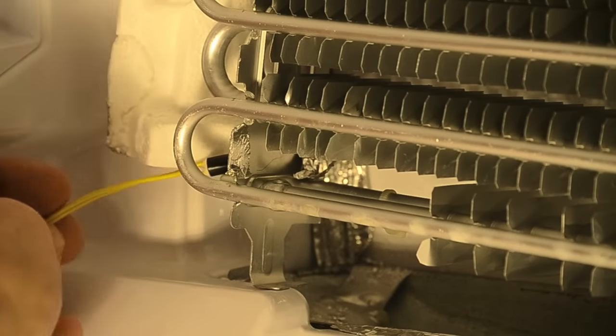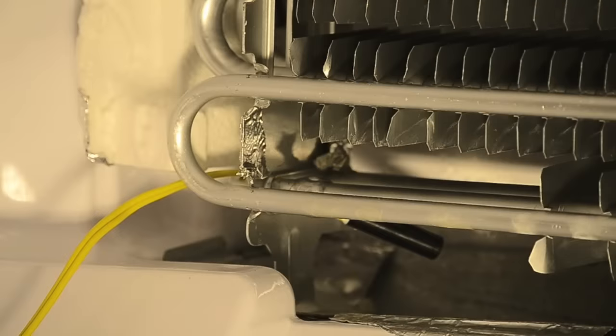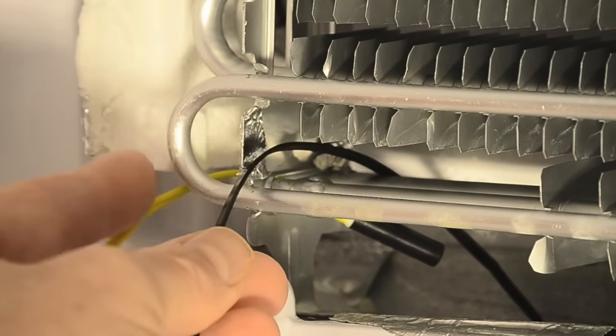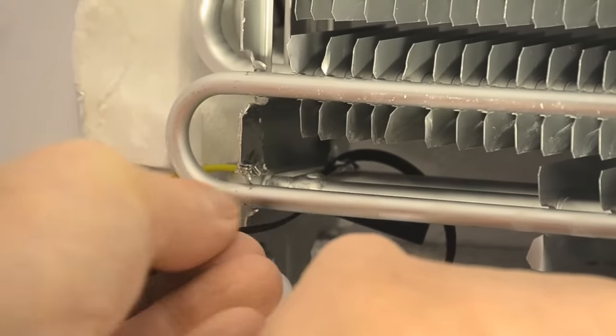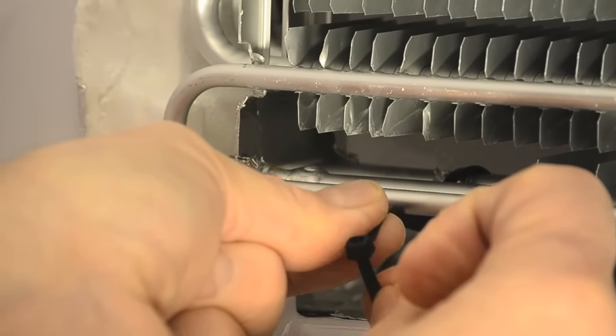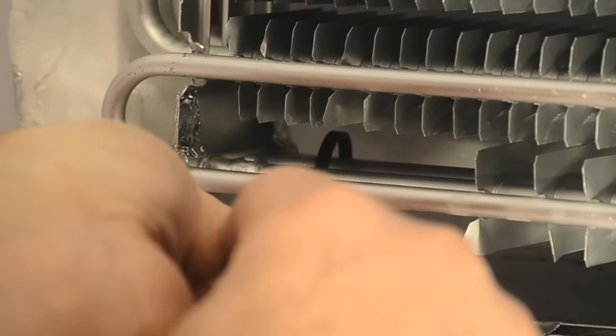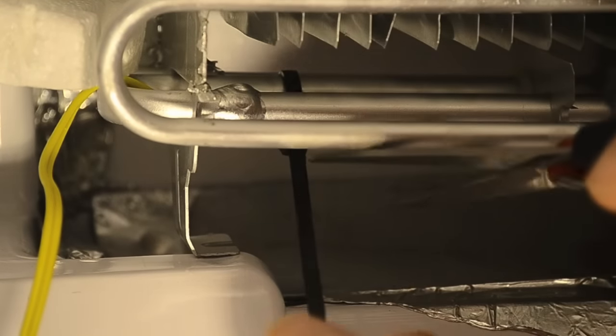Place the new defrost sensor where the old one was. Use a long zip tie to secure it to the coil. You'll need a long zip tie to be able to reach it in the tight spaces, especially underneath the evaporator unit. Snip off the excess. Don't worry about securing it with a second zip tie. It's in a very difficult spot to reach and one should hold the sensor just fine.